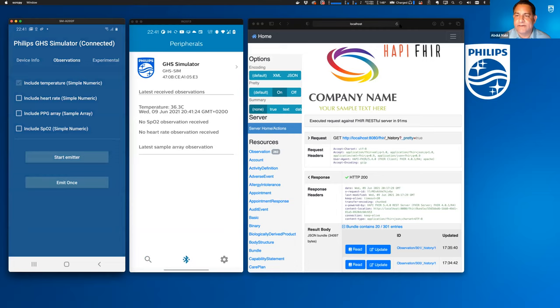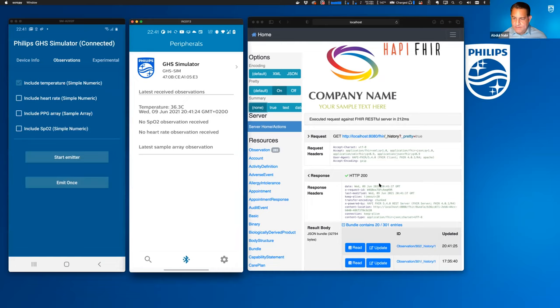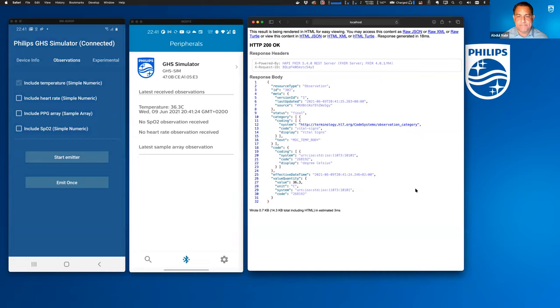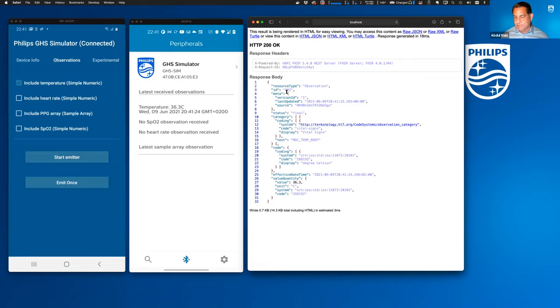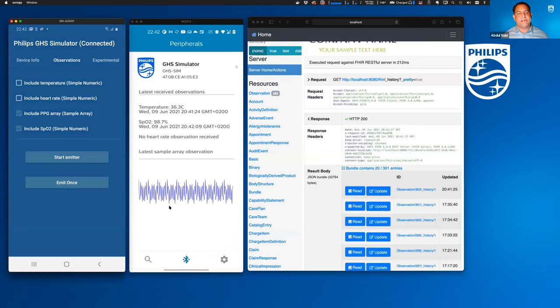It's the demo effect. This needs a good kick. And then if I refresh here, you'll see there's an observation that's come posted into the server. There's a body temperature. As you can see, the ACOM translates very quickly. It's a very thin layer to translate an ACOM object into FHIR and then shoot that up. In the case, we can actually get a little more complicated. Let's do a PPG array and an SpO2. We'll send those. You'll see, I generate a random waveform, and then the SpO2.